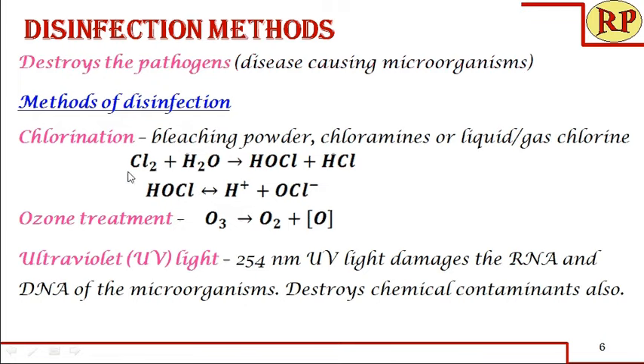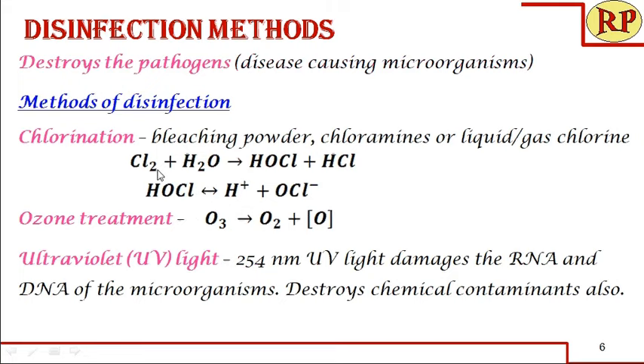When liquid or gaseous chlorine is mixed in water, it forms hypochlorous acid and HCl. The hypochlorous acid deactivates the enzymes present in the microorganisms and destroys them. Once hypochlorous acid is formed, it depends on the pH of the water. At pH 7.5, hypochlorous acid and hypochlorite ion are in equilibrium. Both act as disinfectants, but hypochlorite ion is a very weak disinfectant when compared to hypochlorous acid, so we prefer hypochlorous acid to be present.